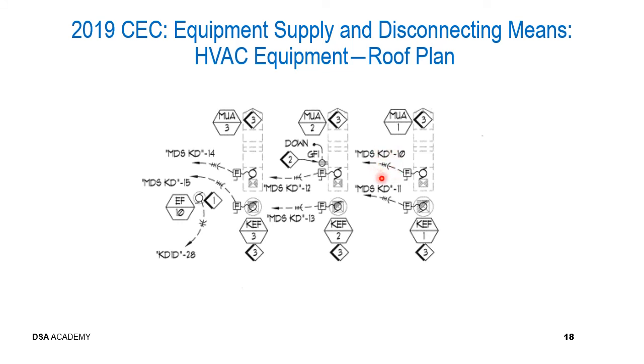This designation also shows here 3 little hashed lines and 1 curved line. The 3 little hashed lines on this home run designation correspond to 3 ungrounded conductors. This curved line identifies the grounded conductor for this circuit, or also known as the neutral. So again, it's important to understand what each of these symbols and all of these words mean.